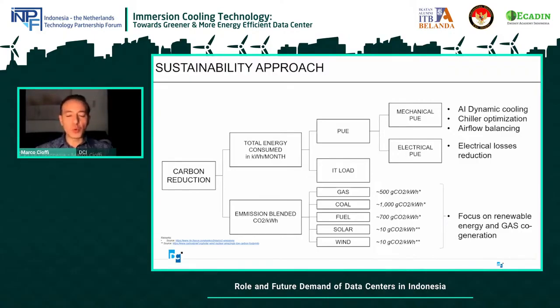But from our side, what we can use is the PUE. The PUE is basically the ratio between the energy we use against the energy the customer uses. To give you some reference, in Southeast Asia it's around 1.8, meaning for every watt of electricity used in a server, you must use 0.8 watt of electricity to cool that 1 watt of IT load.